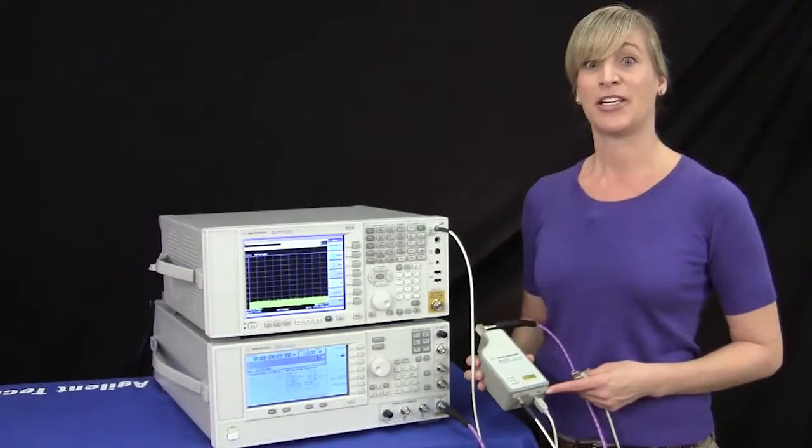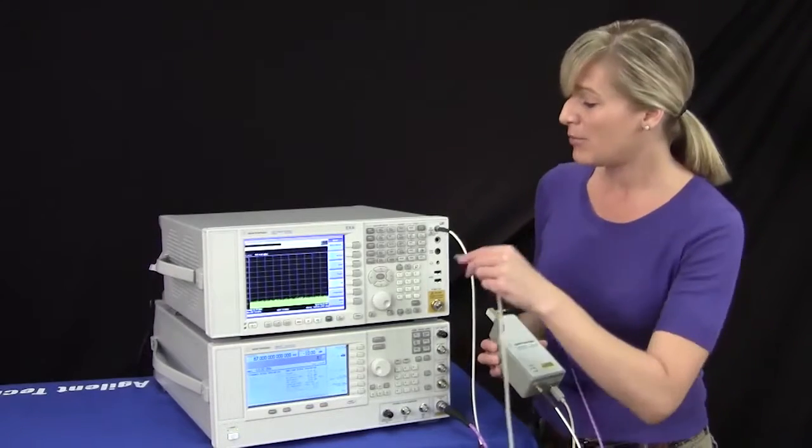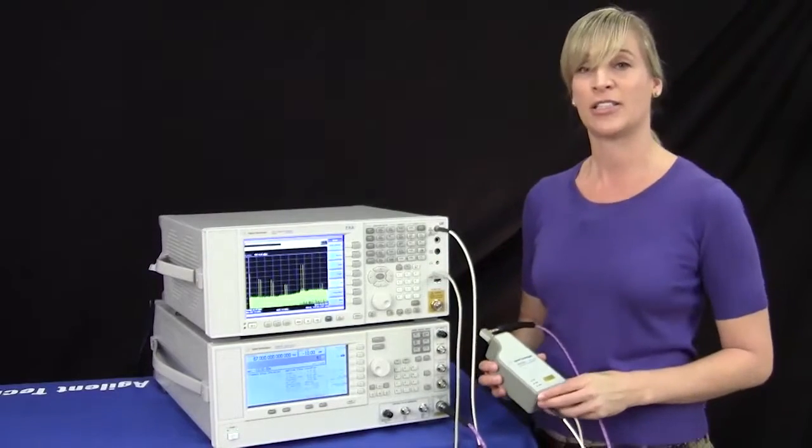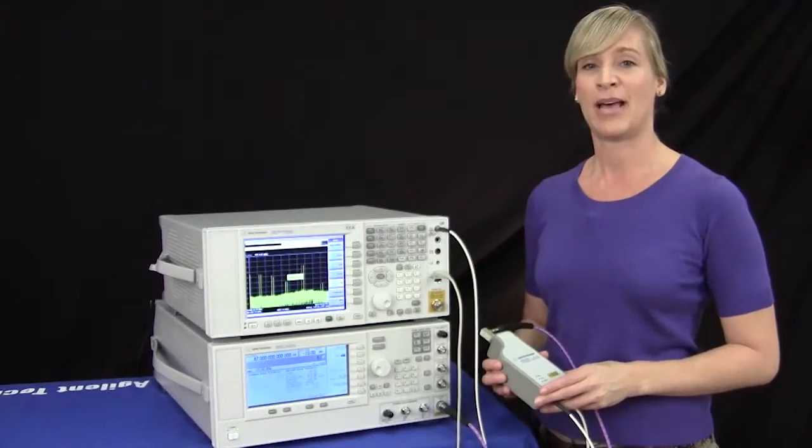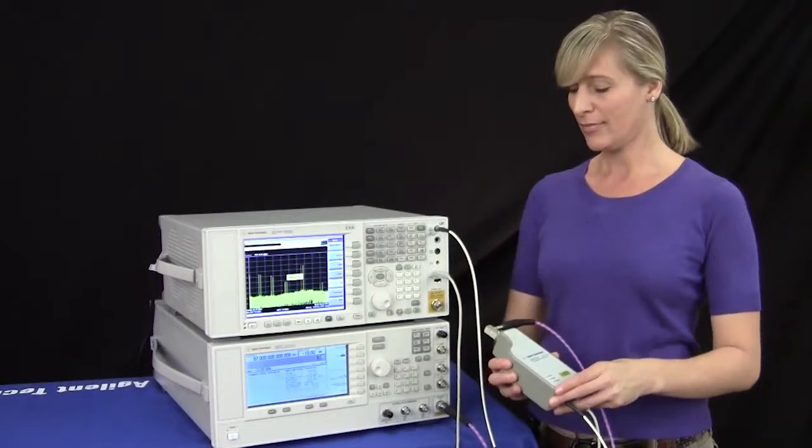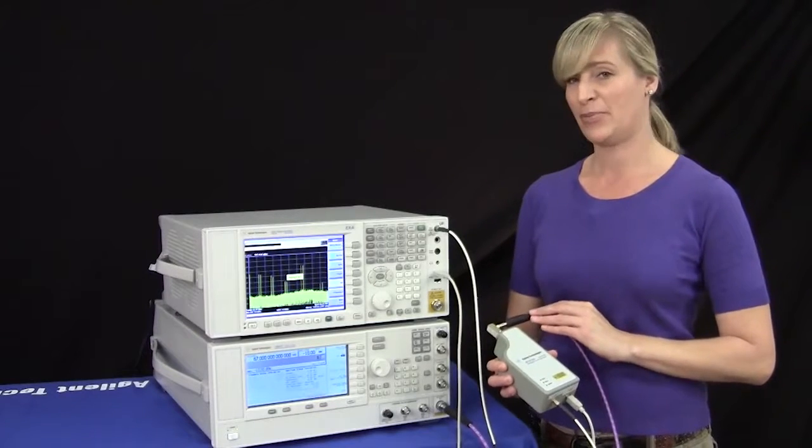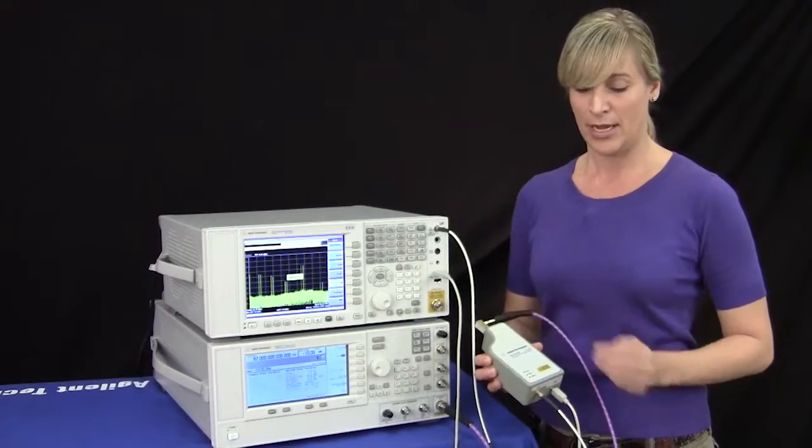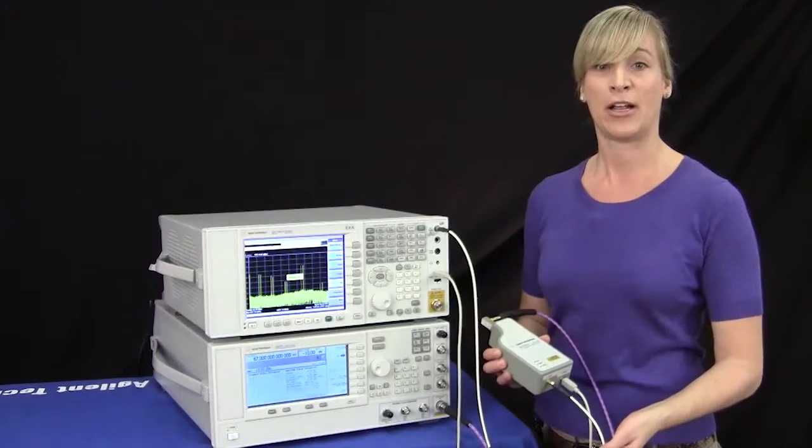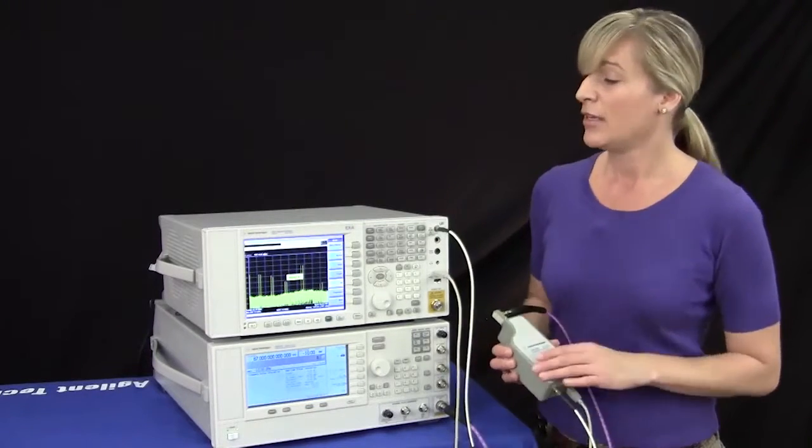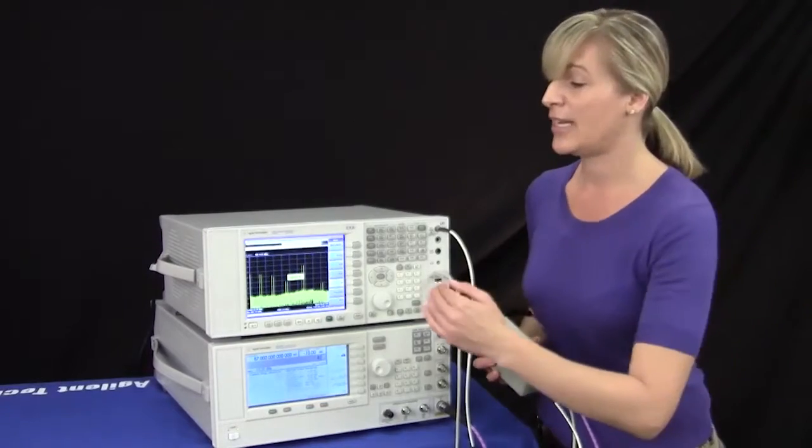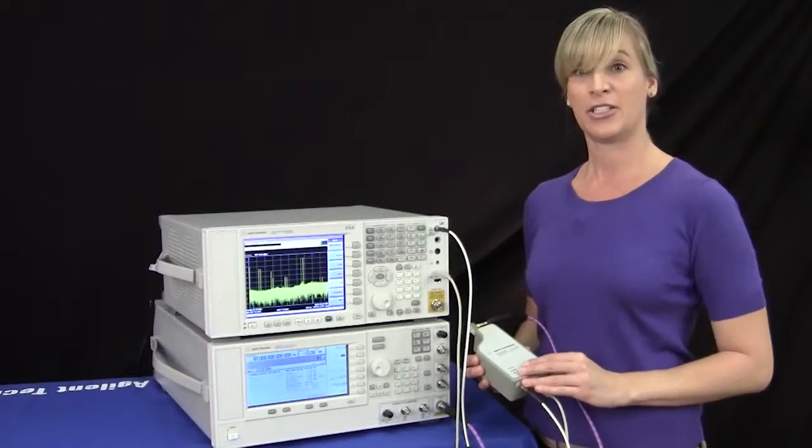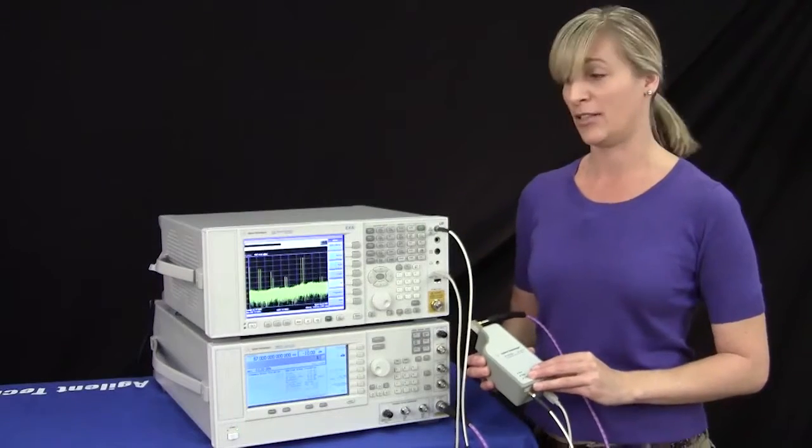The smart harmonic mixer is easy to set up. You simply plug the USB into the USB port of the signal analyzer and the hardware is automatically detected. The RF signal from the PSG is now coming into the input of the mixer and we have a single cable now for the LO and the IF. The EXA automatically sets the display to show the frequency span of the mixer and it adjusts the power level of the local oscillator.